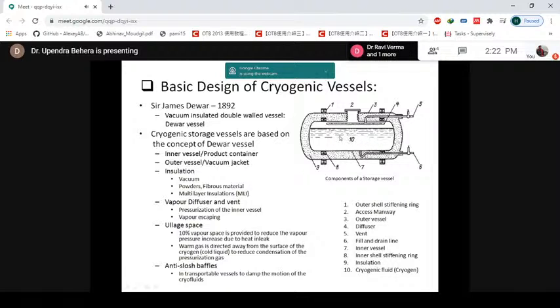This is the place where these cryogens are filled or stored. There is also a vent for whatever boil-off takes place, and for pressurizing the container. You have a vapor diffuser and vent for pressurization of the inner vessel and for escaping vapor. Also, you have a vapor space here on all cryogenic containers, even though they mention the container capacity is, for example, 55 liters.